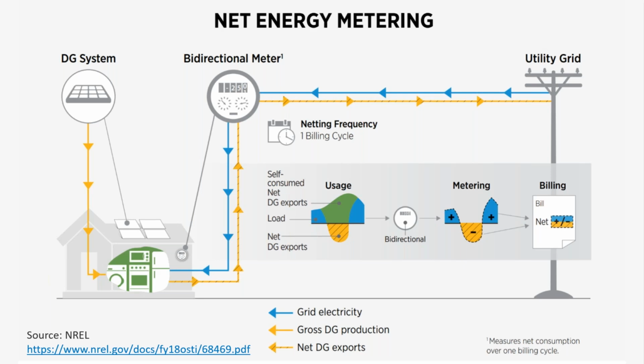And you can see in the gray box, there's the usage, which shows your load that you get from the electricity, which is blue. There's that which was self-consumed, which is the green, and then there's the orange, which is what was exported to the utility. Because of the bidirectional meter, that which was used and self-consumed is not monitored, and that which is exported is. So under the metering, you use the blue boxes and you export the orange. Therefore the difference between those two gets to what your total bill is.